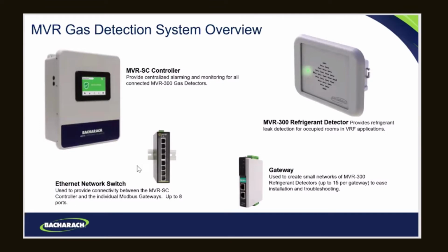These are the basic pieces. You've got the controller, which is going to be all the centralized alarming and configuration. You've got an Ethernet switch. We sell an Ethernet switch, or you can buy an Ethernet switch off the shelf. It's just an Ethernet switch. These gateways are kind of important, and this is our Ethernet to 485 converter. So we're taking Ethernet signals and getting them to a Modbus RS485 network, and then that's going to connect into the MVR-300. So these are the basic pieces of the entire network. Obviously, the MVR-300 is in your occupied space or your room, and these other pieces can be remote from that, however you want to lay it out.